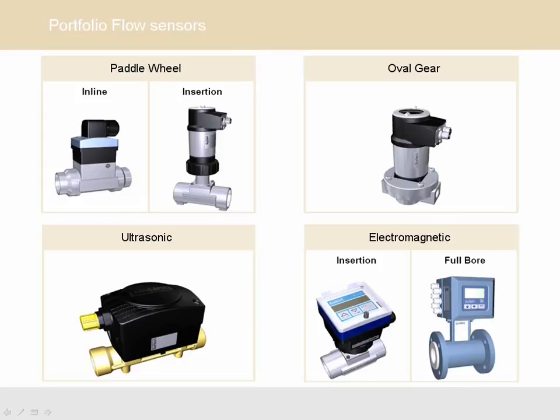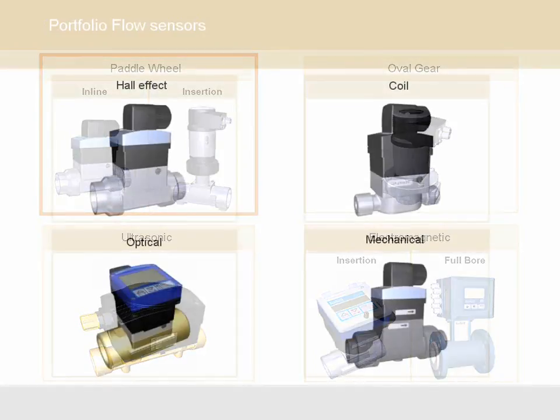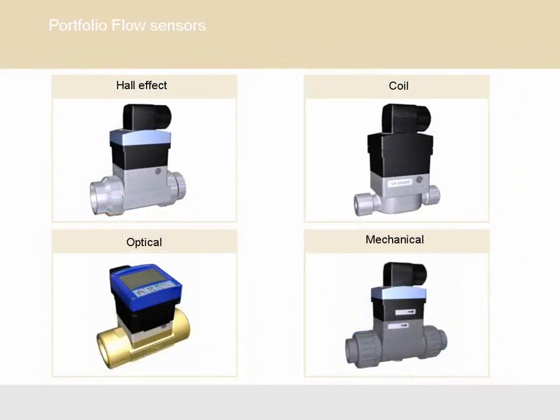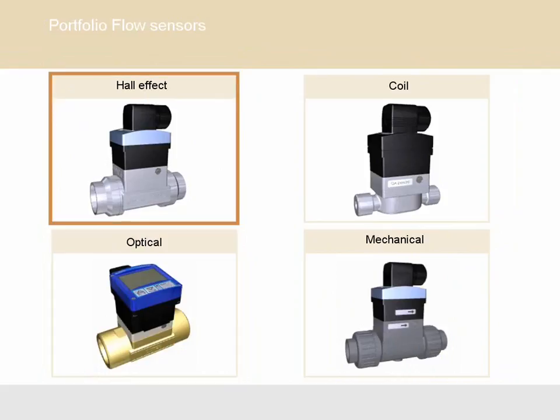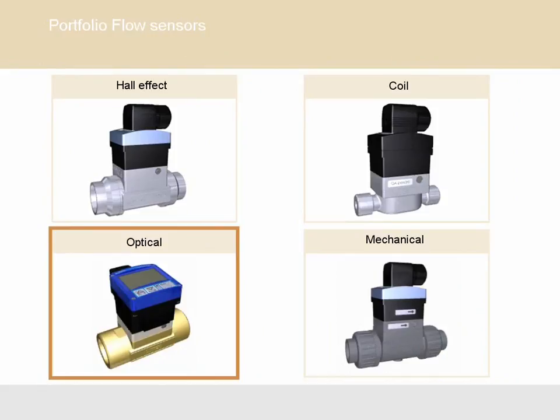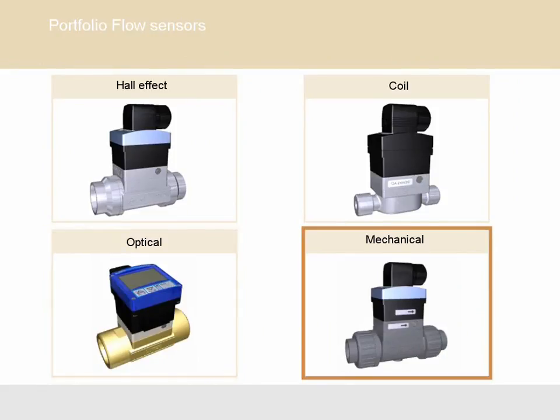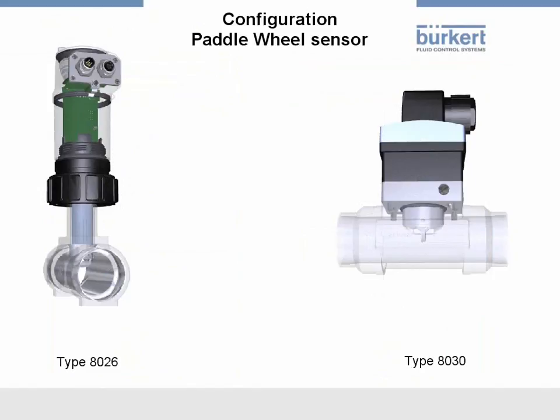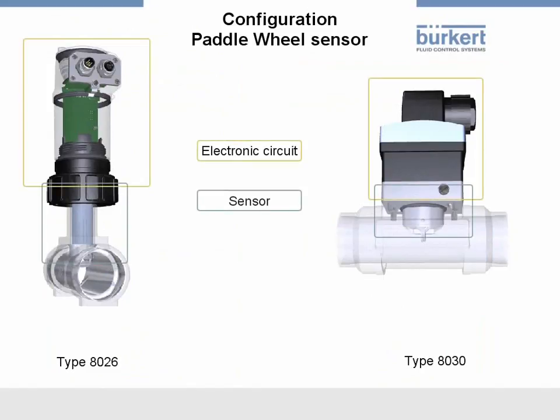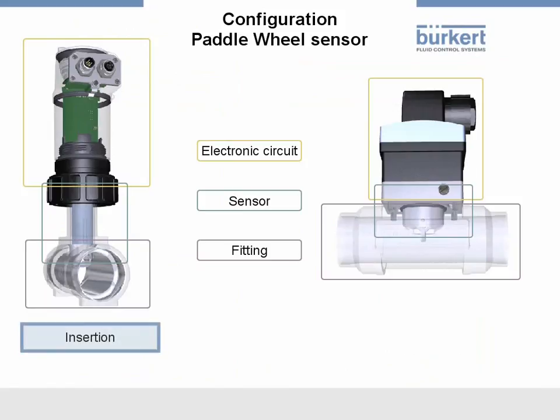We'll now examine each of these measuring principles more closely. Let's start with the paddle wheel principle. The sensor is available in several sub-principle versions: Hall effect, coil, optical, or mechanical paddle position signal detection. A paddle wheel flow meter consists of an electronic circuit, the sensor, and the fitting, which is available in insertion and inline versions. Both the inline and the insertion fittings are available in different materials and with different process connections.